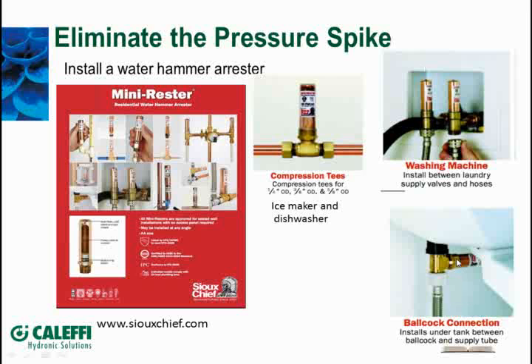You can see here's one that goes right on the bottom of a toilet, a ball cock, because they can cause a pressure spike like that. And then they have these that you can just put inline somewhere, so this can maybe go over to your ice maker. But if you've got a job where you've got a chronic backflow preventer leak, that you go back and switch out again and again and again, something's causing that to happen. They're not all bad backflow preventers, and it's best to find the cause.